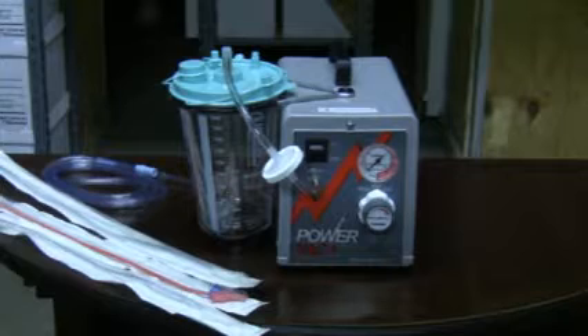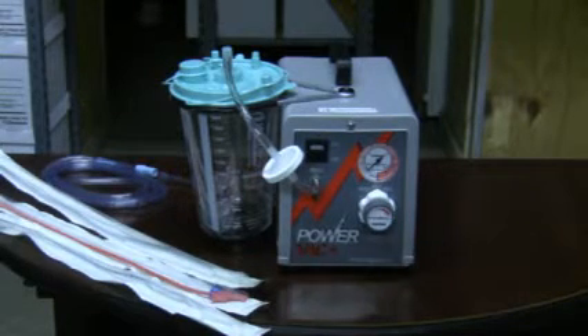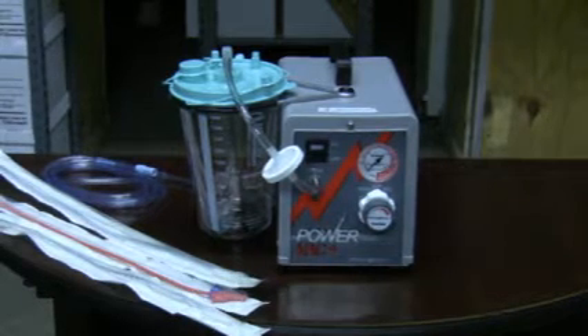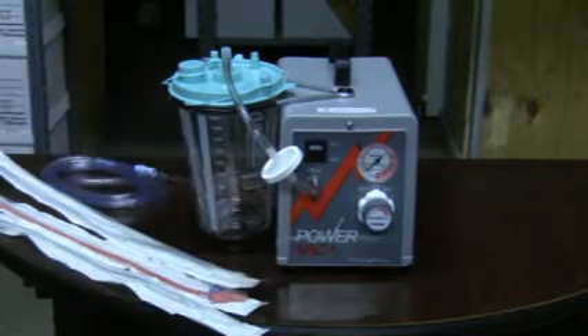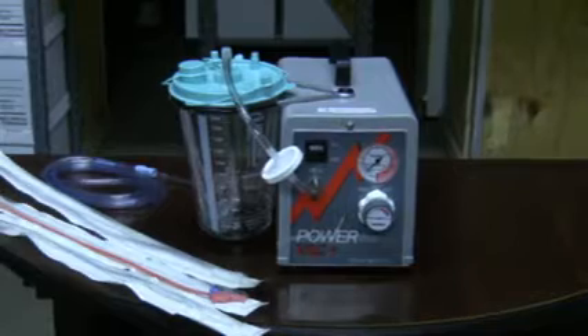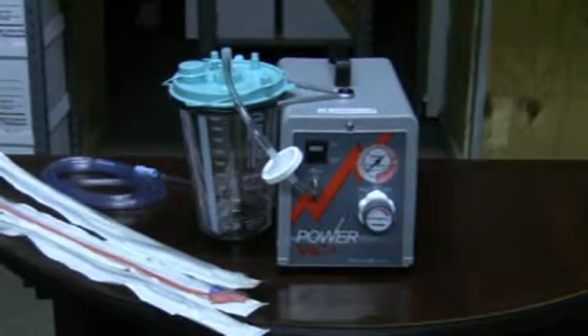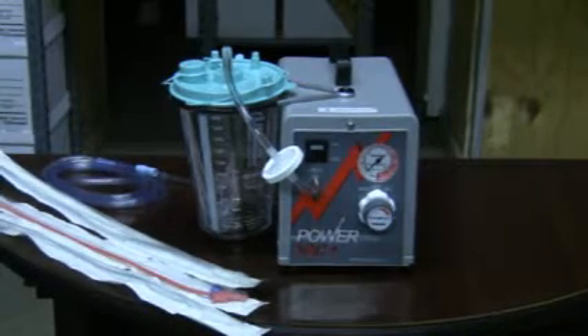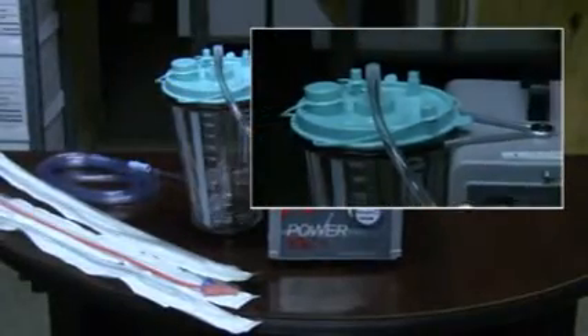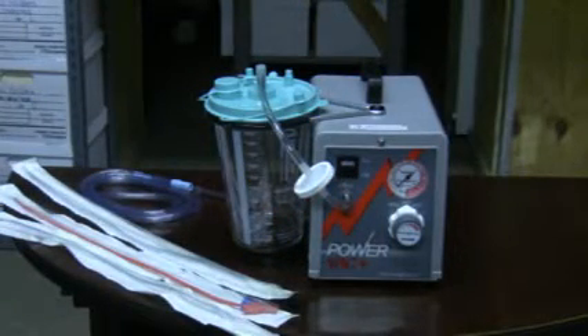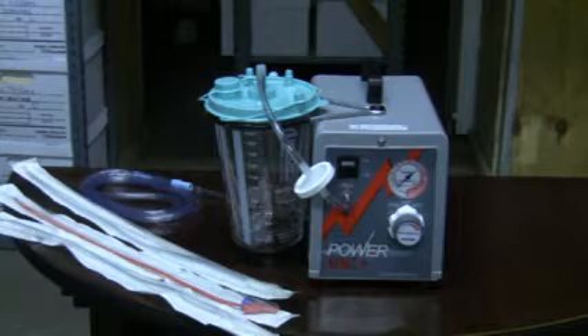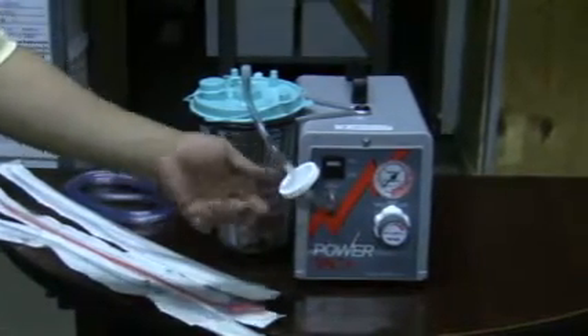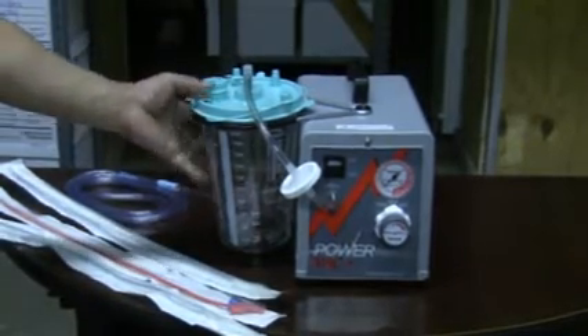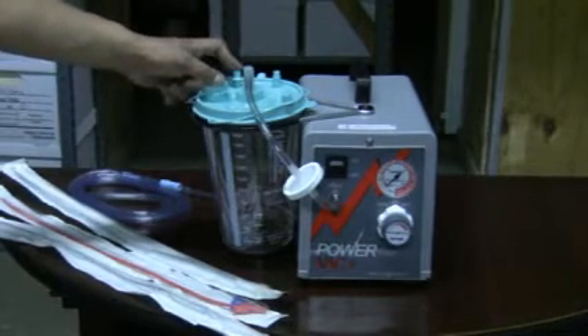After you plug your intermittent suction machine into your grounded electrical outlet for proper and safe function, you proceed to check your suction canister for any cracks, and to make sure the lid is completely sealed. Your hydrophobic filter is connected to the outlet on the front of your intermittent suction machine in the proper direction, as well as connected to the port on the top of your center cap of your lid. All other open ports which will not be used are capped off as well. You may double check before placing in the on position. After double checking all of your connections, as far as your grounded electrical outlet connection for power, your connection for your hydrophobic filter to the front of your outlet in the proper direction to the top of your canister lid, the suction canister lid is completely sealed, with all open ports that will not be used also sealed and capped off.